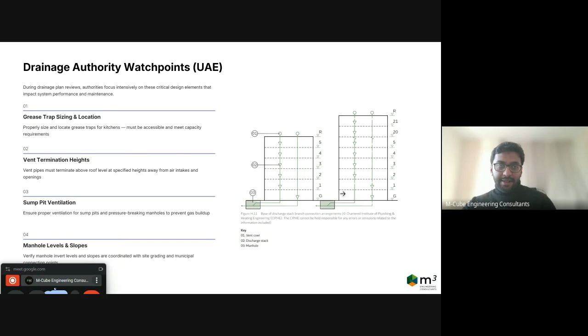Moving forward, some key watch points we generally miss in design: grease trap sizing and location. When doing designs for Sharjah, it's mandatory to have a grease trap wherever there's a kitchen, and wherever there's a commercial space or commercial retail outlet. Restaurants also come up, so identifying this at the beginning is very important.